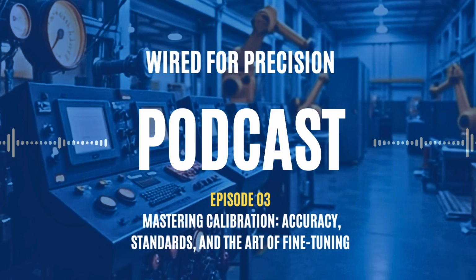In simple terms, calibration is the process of comparing a measuring instrument to a known reference, usually a standard with a known accuracy, and adjusting it if necessary to align its output. In industry, calibration is not just a best practice, it's a requirement, especially in sectors like pharmaceuticals, oil and gas, food manufacturing, and aerospace, where even the smallest deviation can lead to compliance violations, downtime, or worse, safety risks.